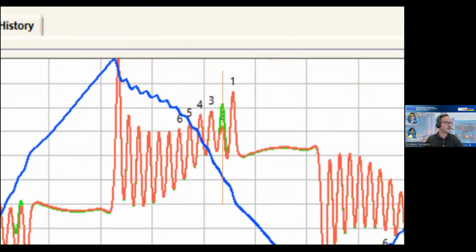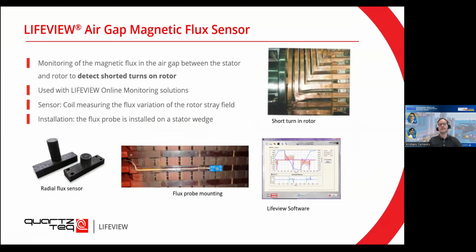And just a bit of a zoom in to what I explained previously. To sum it up, monitoring the magnetic flux will help you determine shorted turns on the rotor. As you can see in the image on the top right, the installation is quite straightforward. You have one sensor, a coil measuring the flux. You install it in the slot, in the wedge. Once the machine starts up, you're going to measure each of the coils. And as I showed you in the software, you're going to see these peaks, and these peaks can be compared to each other to see if there are any shorted turns.